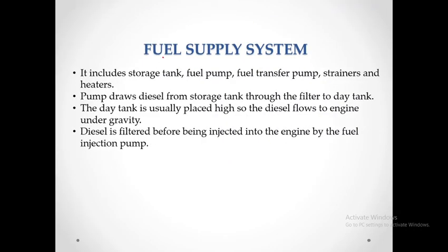Then is the fuel supply system. It includes the storage tank, fuel pump, fuel transfer pump, strainers and heaters. What happens here is the pump draws the diesel from a storage tank through the filter to a day tank. The day tank is usually placed high, so the diesel flows to the engine under gravity. The day tank will be placed high compared to the diesel engine, so that the diesel easily flows to the engine under gravity.